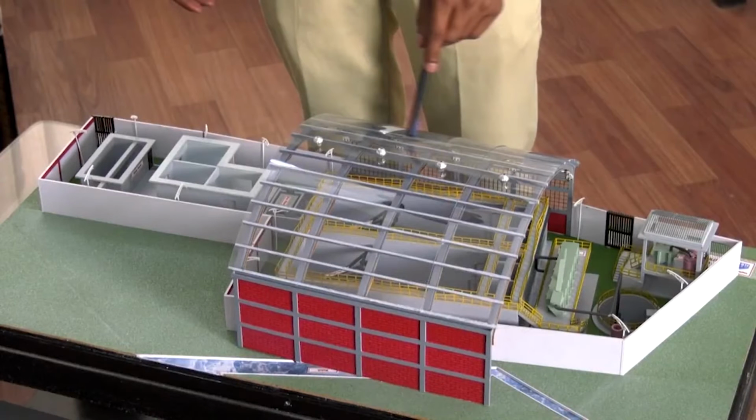So, these are called the bioselector tanks. So, what do we have? These tanks with high strength wastewater. You have some sludge or microbes that are put in, and they are aerated for some time, let's say 15 minutes, right? And so you have air, oxygen, so it's aeration, and aerobic conditions for most of the time, and then you have a lot of food for the microbes, and you have some microbes because you are putting in microbes too. We'll look at that. So F by M is high in this particular bioselector tank. So the kind of microbes that thrive there are going to lead to rapid degradation, the kinetics are going to be faster, and the kind of microbes that we want are typically going to thrive there, right?